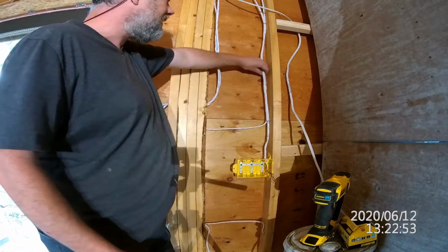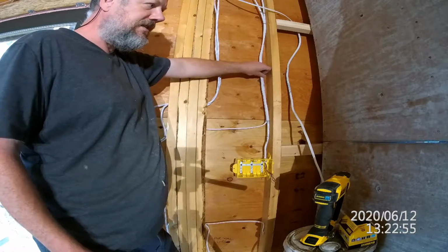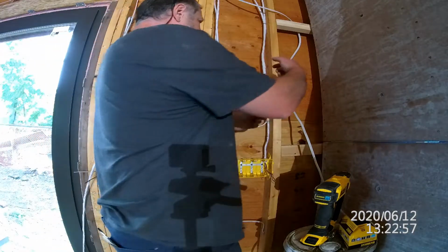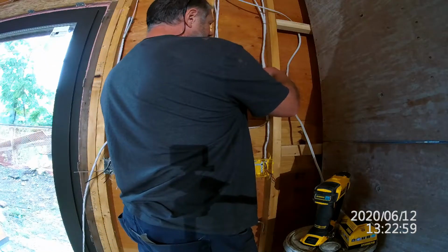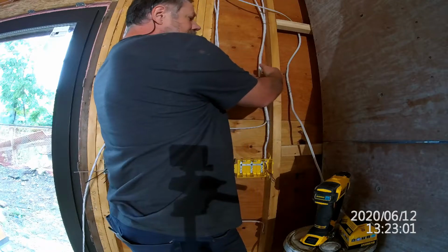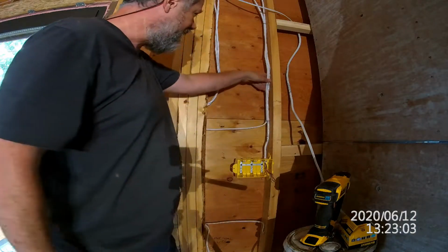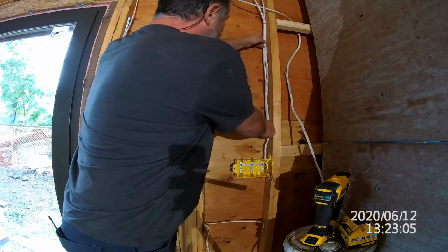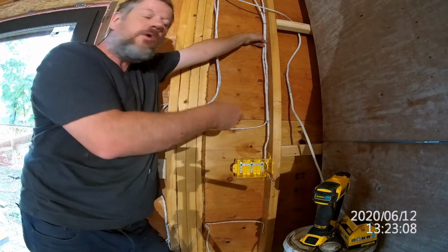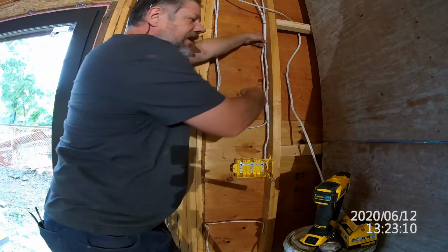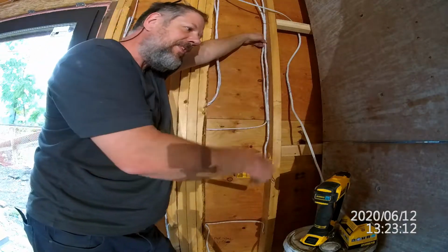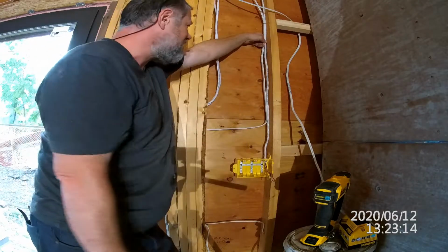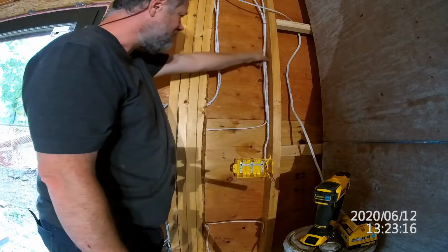The second reason you want it to be flexible is if you drive a nail or a screw in here and it starts to miss, the cable will move out of the way. If it was super tight and couldn't move at all, you would end up scoring the outer sheathing and most likely the inner conductor sheathing, hitting the copper.